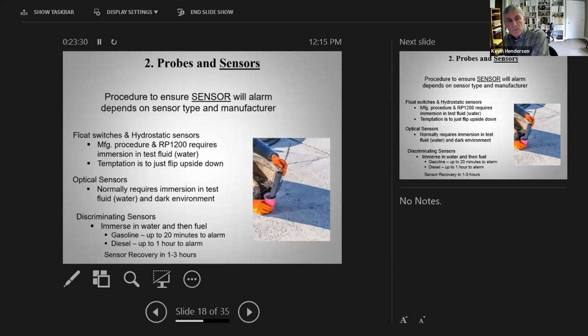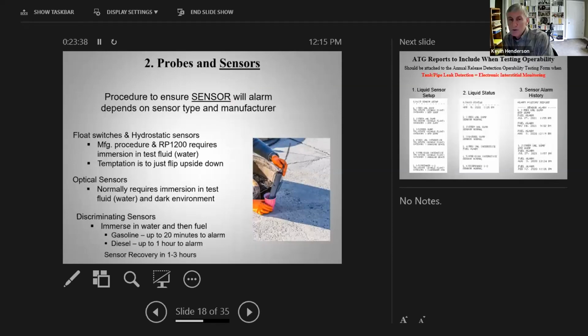So the test procedure is really, really simple on a float type switch. Again, in the old days we would just go out and pick the sensor up, turn it upside down, causing the float to move up, and make sure that it triggered the alarm. And of course, there are people who will still do that, but that is not in accordance with the testing requirements for PEI RP 1200 or any manufacturer's procedure. RP 1200 would tell you that you have to submerge the sensor in a test fluid. Typically, that's just water because they're non-discriminating sensors. So you take the sensor out of the sump or out of the tank interstitial, place it in the test fluid, and verify that it does go into alarm.